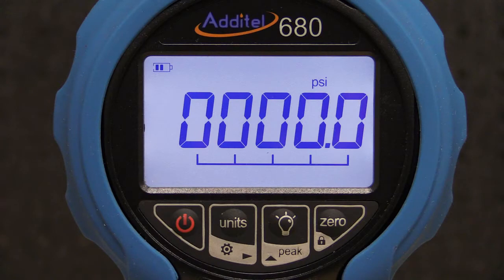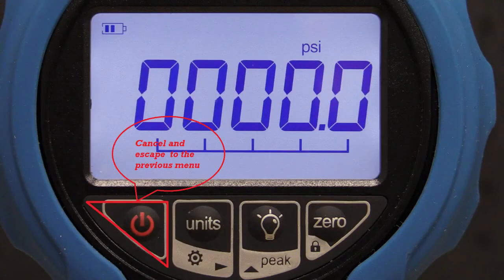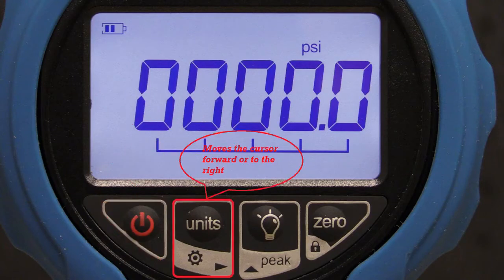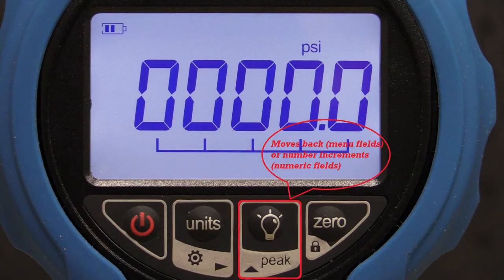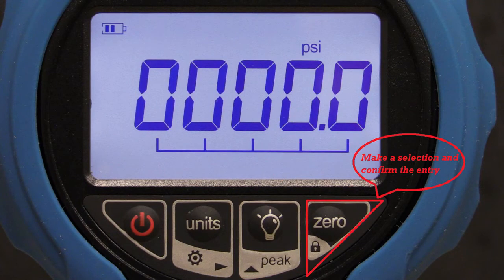In order to navigate the ADT680W menus, it is helpful to understand the secondary functions for each key. When in the menu, the power key cancels and escapes to the previous menu. The units key will move the cursor forward or to the right. The backlight key will move the cursor backward when in the menu, and increments the number when editing a numeric field. The zero key is used to make a selection and confirm the entry.